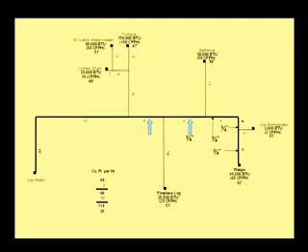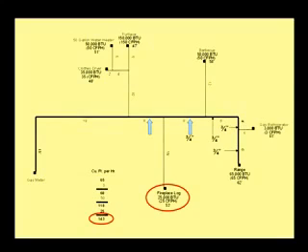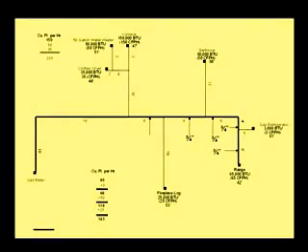The next section of pipe will be supplying the branch to the fireplace log, which has a demand of 25 cubic feet per hour, plus the 118 cubic feet per hour from the previous appliances, for a total demand of 143 cubic feet per hour. Refer to table 12-8, 70-foot row — 143 will fit under 237 — and see that a 1-inch pipe will accommodate the 143 cubic feet per hour demand for the 6-foot section.